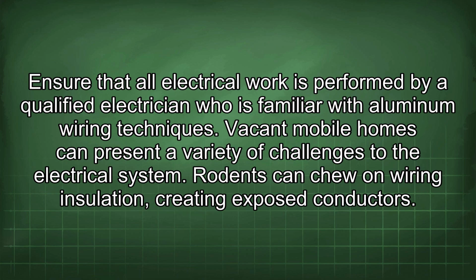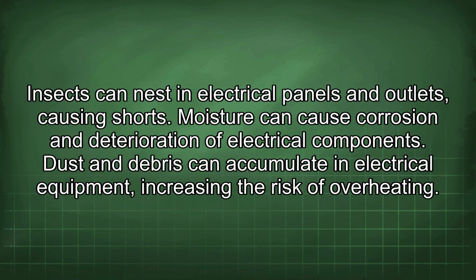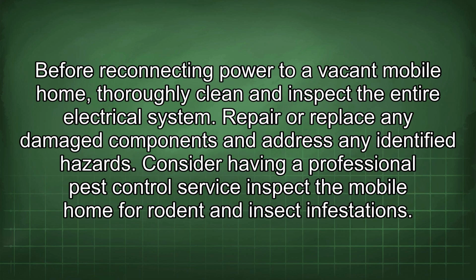Vacant mobile homes can present a variety of challenges to the electrical system. Rodents can chew on wiring insulation, creating exposed conductors. Insects can nest in electrical panels and outlets, causing shorts. Moisture can cause corrosion and deterioration of electrical components. Dust and debris can accumulate in electrical equipment, increasing the risk of overheating. Before reconnecting power to a vacant mobile home, thoroughly clean and inspect the entire electrical system. Repair or replace any damaged components and address any identified hazards. Consider having a professional pest control service inspect the mobile home for rodent and insect infestations.